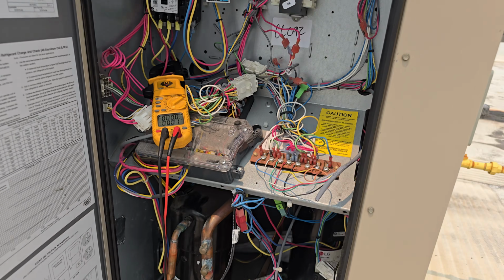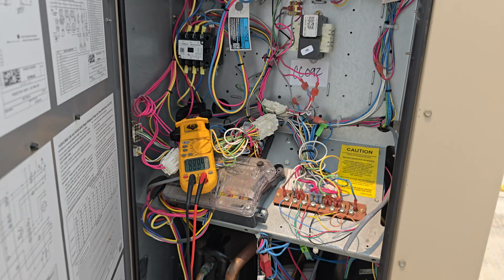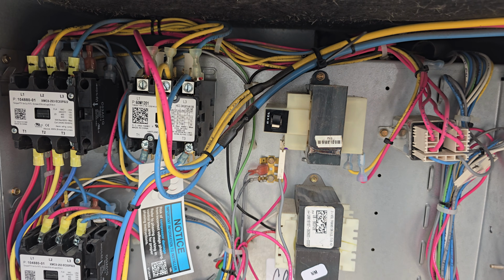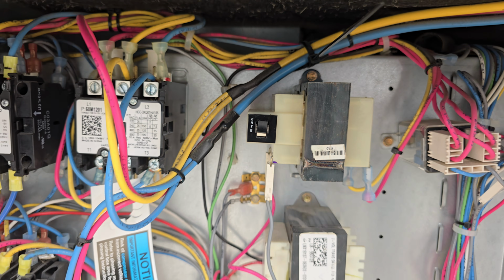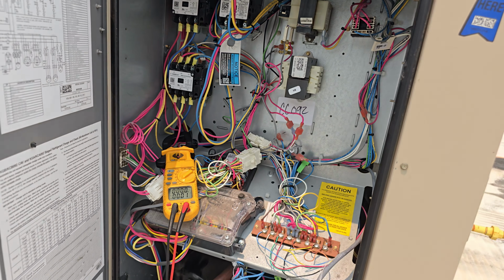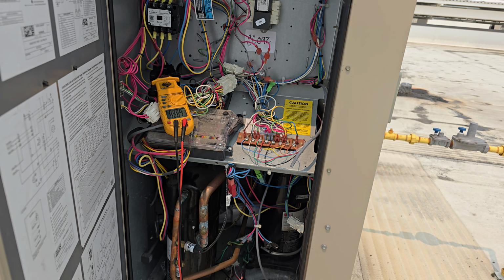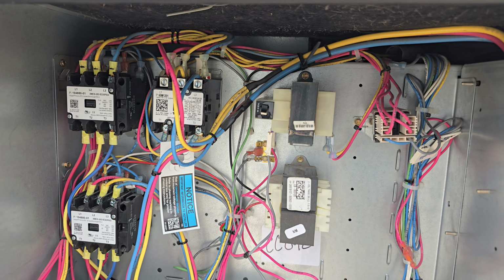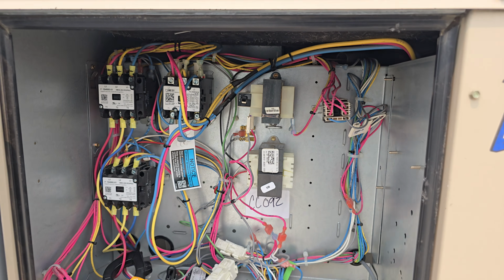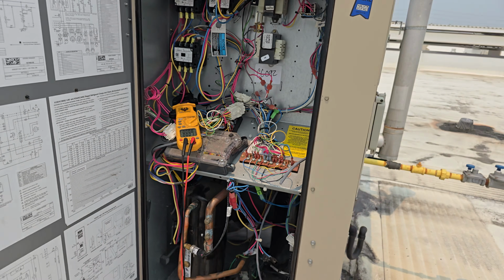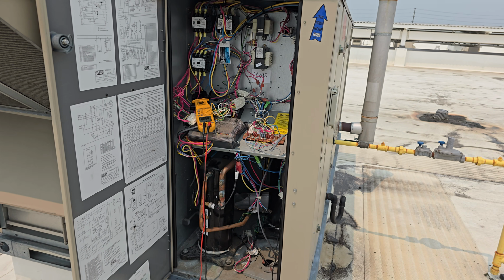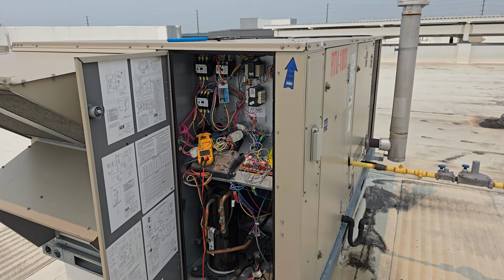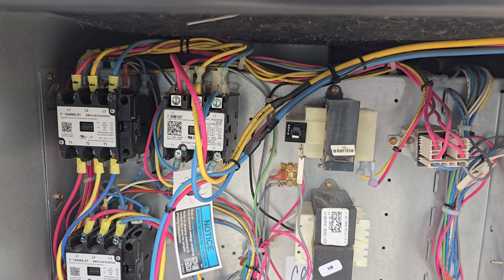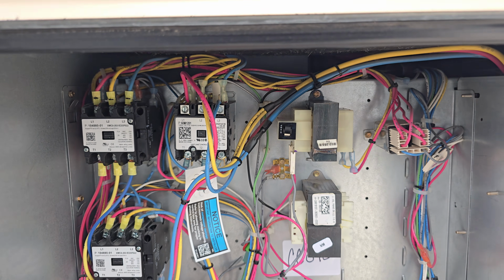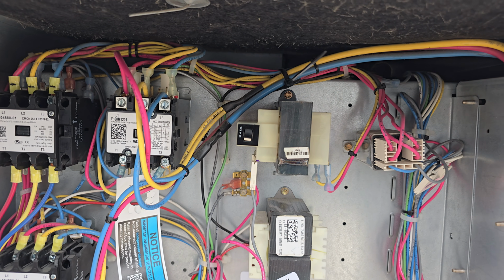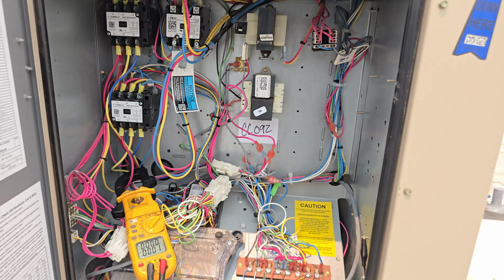I can hear my fan kick in, and my compressor, oh boy, okay. See, the compressor was about to kick in, and then this tripped off right away. Remember, this is happening on the low voltage, not on the high voltage. If it were on the high voltage, my breaker or fuse would be tripping off. But because it's happening on the low voltage, only the transformer is tripping off. So what could be happening? Stay tuned, and I will walk you through how to troubleshoot and see what's happening here.